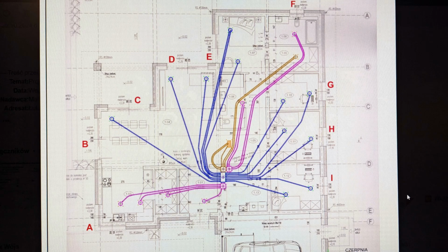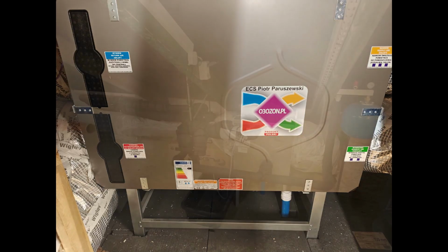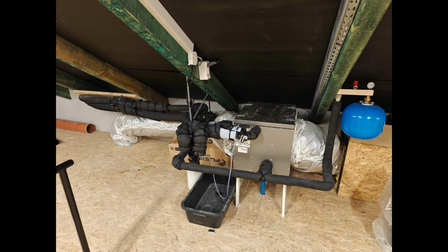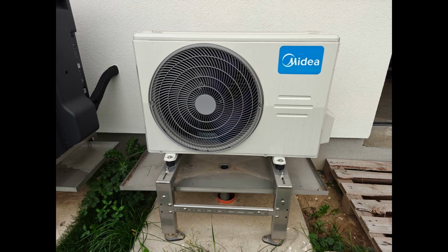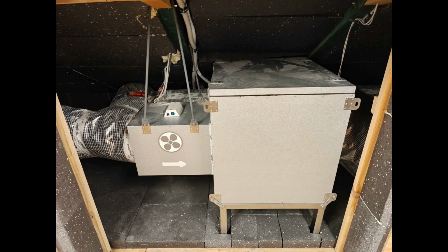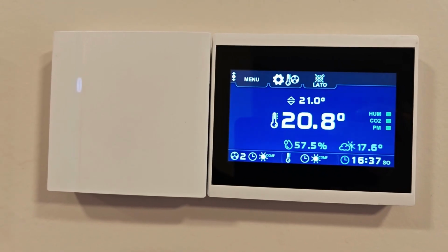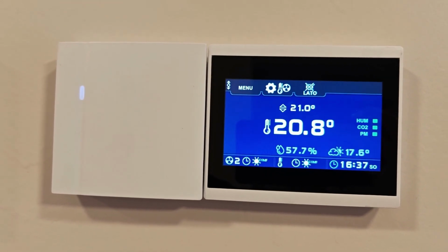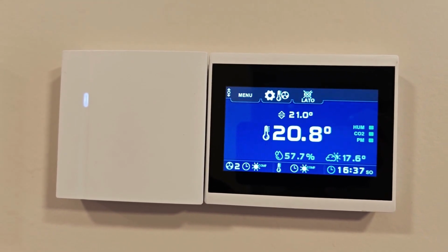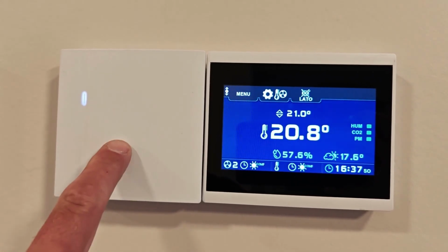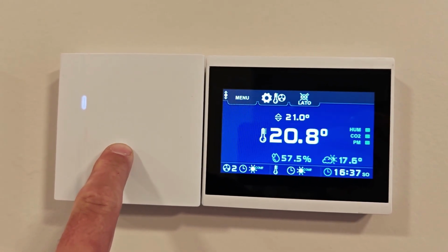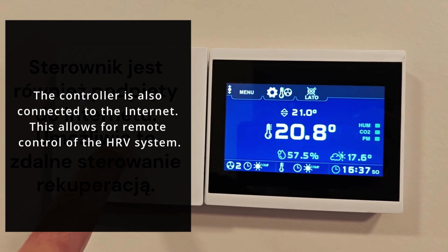Good morning. I would like to present to you my HRV system, which consists, in addition to the recuperator itself, of a glycol heat exchanger and ducted air conditioning based on a condenser unit and a freon heating/cooling coil. I also have an additional carbon and dust sensor connected to the Compit controller, which is located in the living room. This is that sensor.